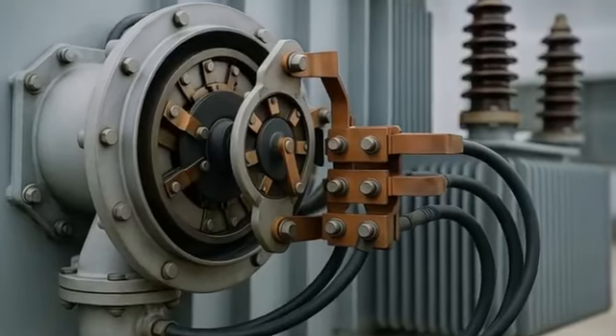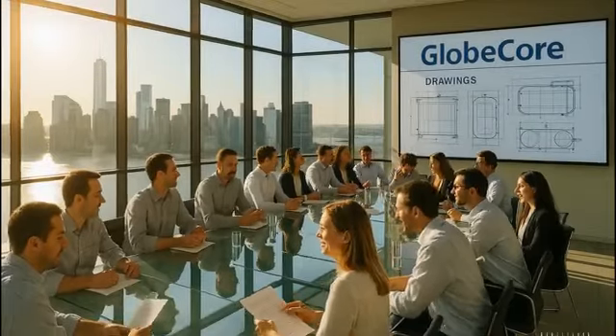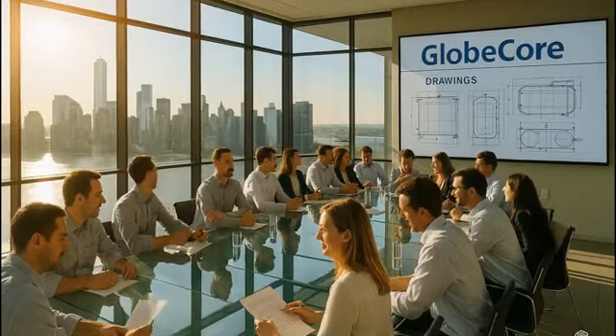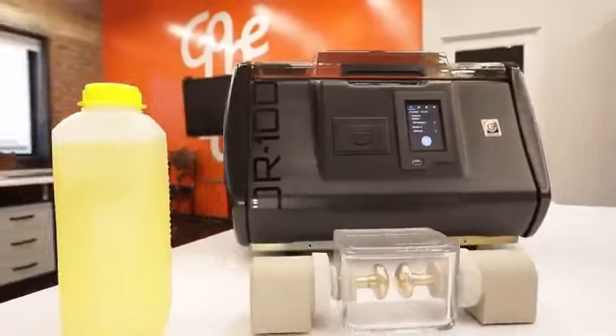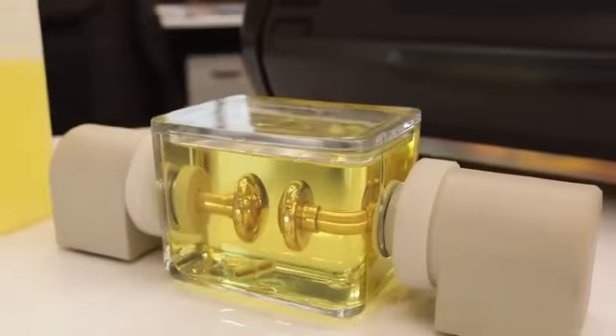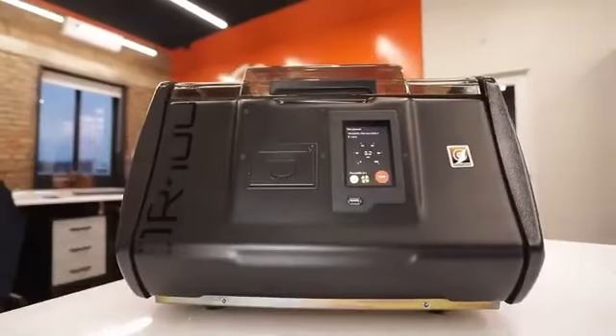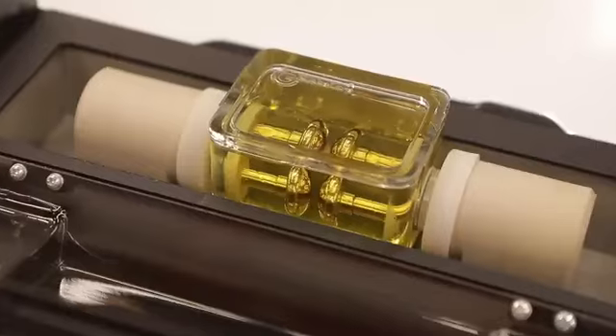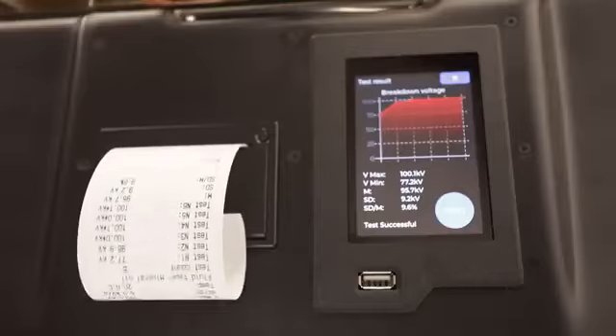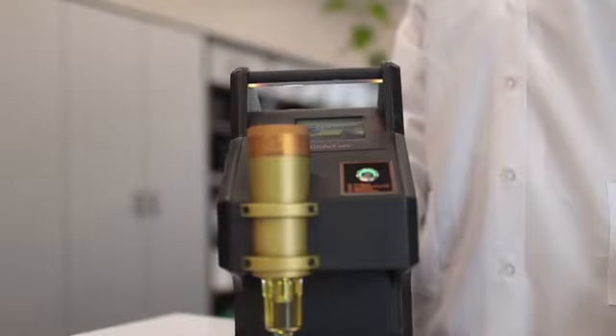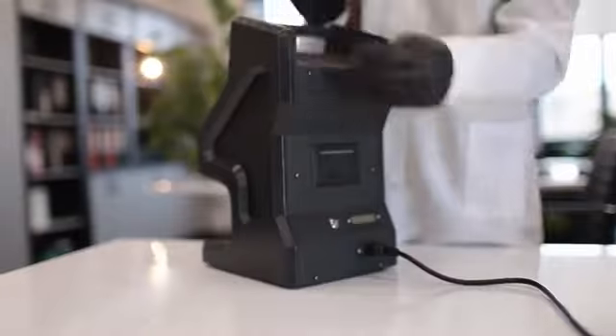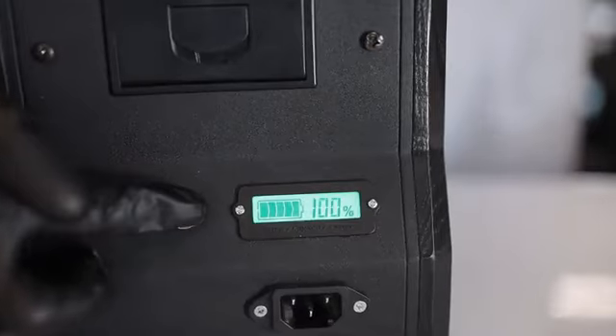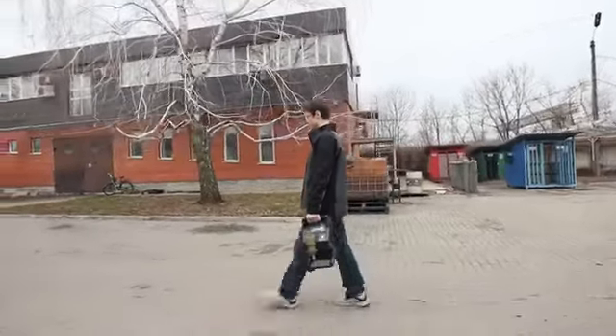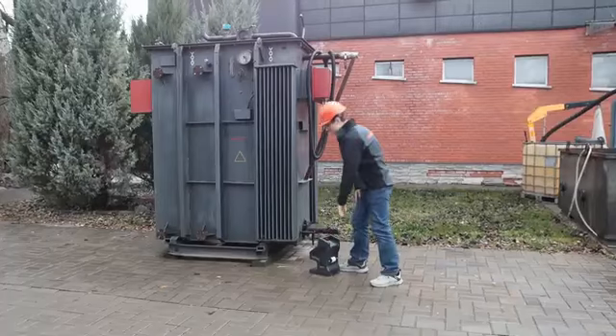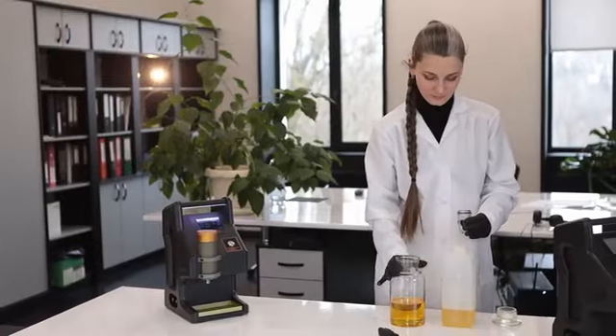In order to monitor the breakdown voltage, GlobeCore recommends using specialized Tor instruments. These instruments allow testing the oil with a maximum breakdown voltage of 60, 80, or 100 kV. While it is recommended to monitor the moisture content by means of Tor1 Express tester. One of the important features of Tor testers is the ability to use them in the field, which is facilitated by a built-in battery. The actual testing process is performed automatically and speedily, allowing you to timely detect any deviations in oil parameters and take the appropriate measures.